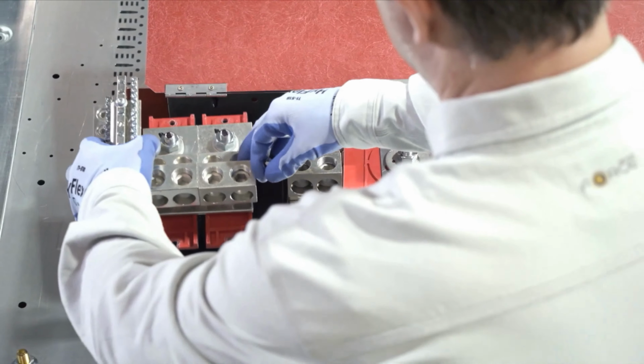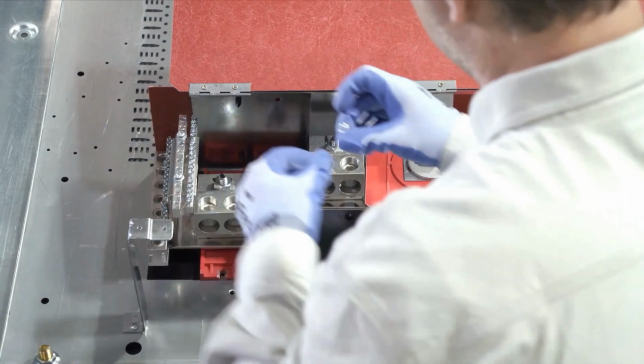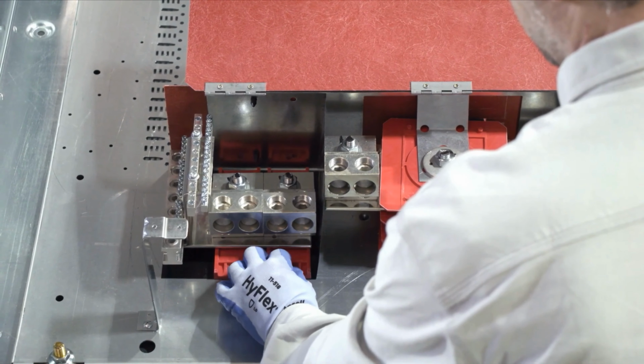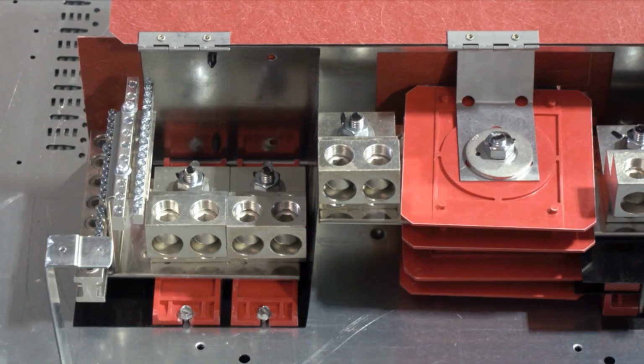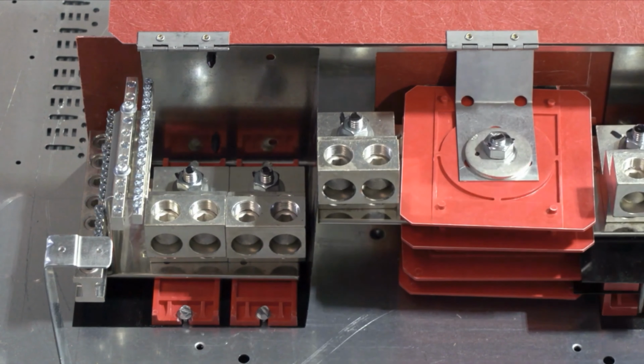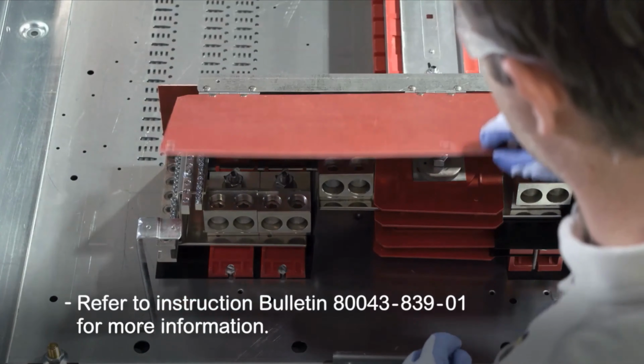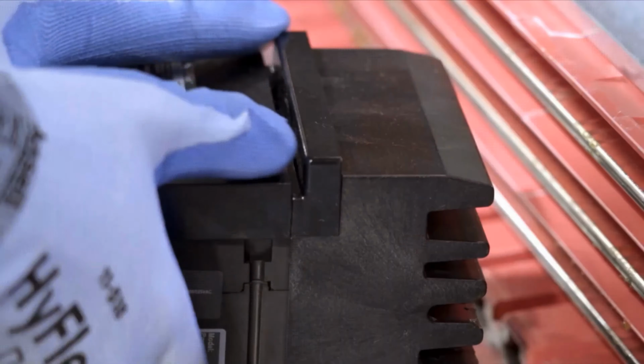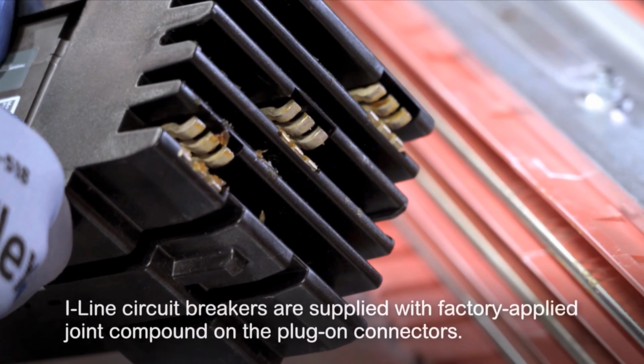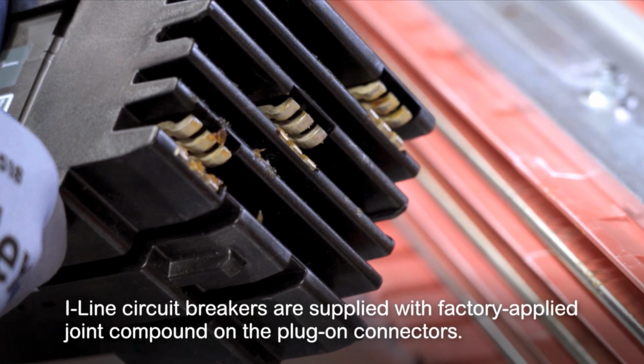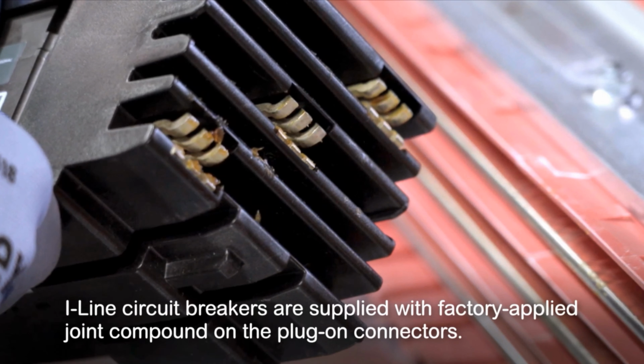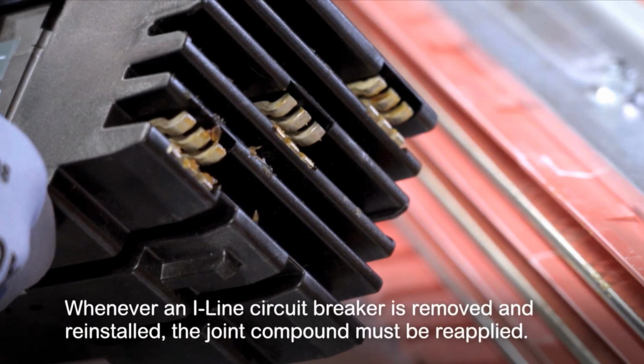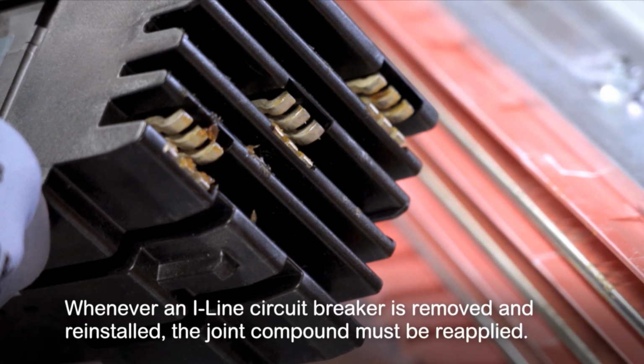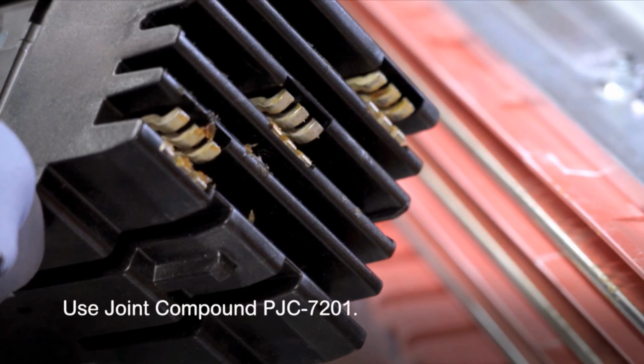Next, to easily install the solid neutral into the I-line power distribution panel board, first lift the red cover, place the solid neutral as shown, and tighten with the supplied hardware. If used as service entrance equipment, the included neutral bonding strap will be required by your contractor, so be sure to include it with your shipment. Additionally, a service entrance barrier kit will also be required. Refer to Instruction Bulletin 80043-83901 for more information. Be aware that the I-line circuit breakers are supplied with factory-applied joint compound on the plug-on connectors. That compound should not be removed because it contributes to the overall performance of the connection. Whenever an I-line circuit breaker is removed and reinstalled, the joint compound must be reapplied. Use joint compound PJC 7201.